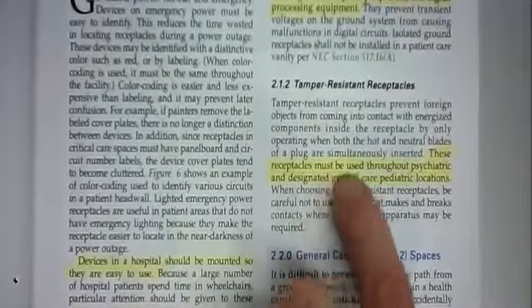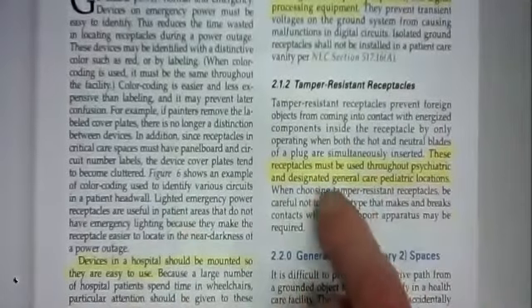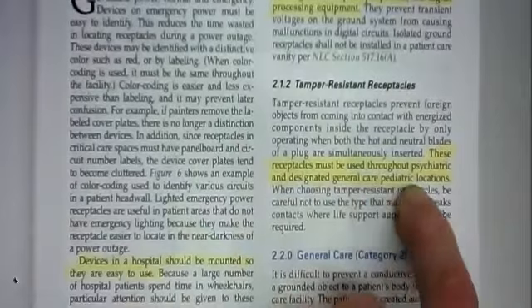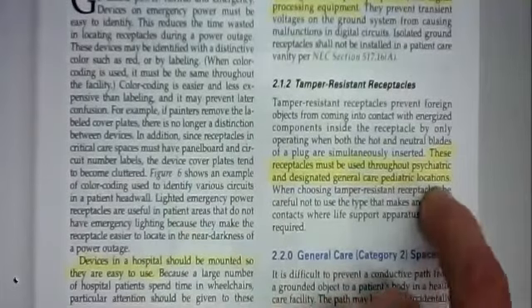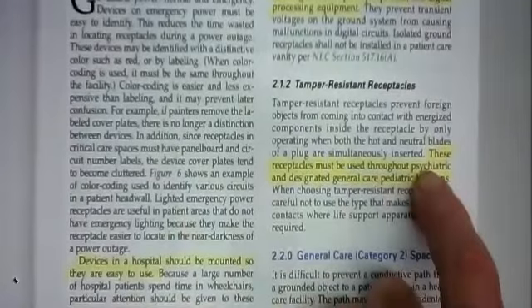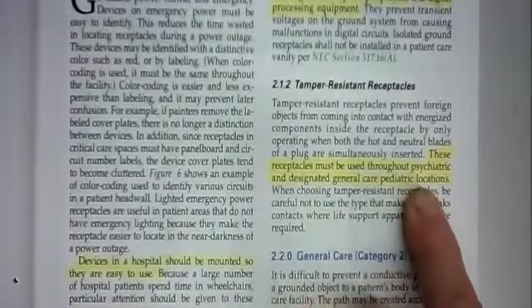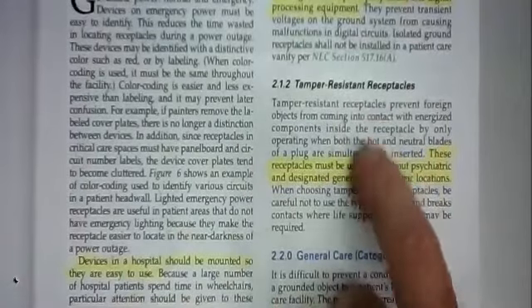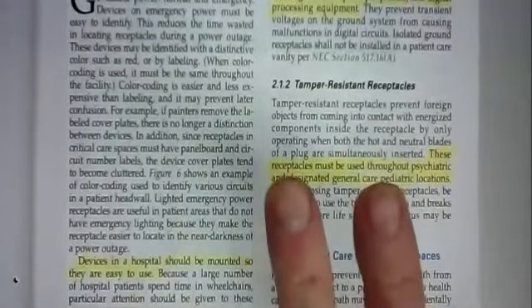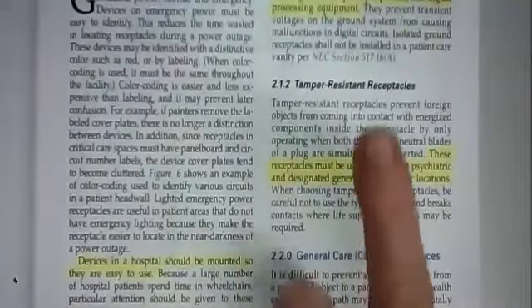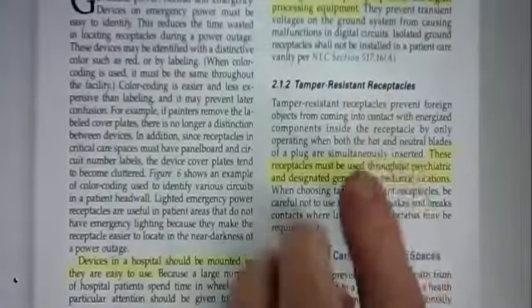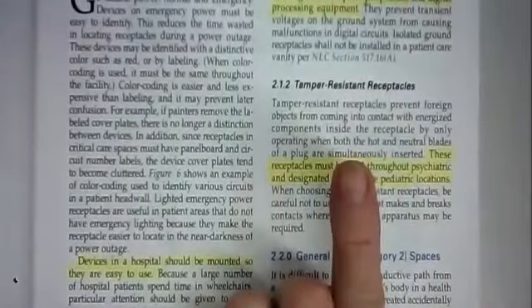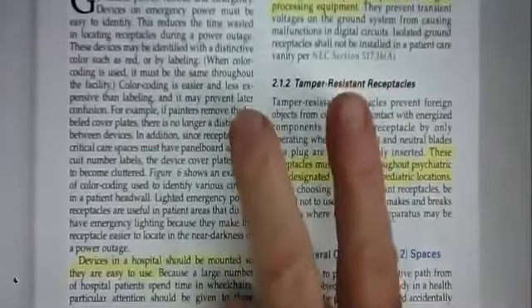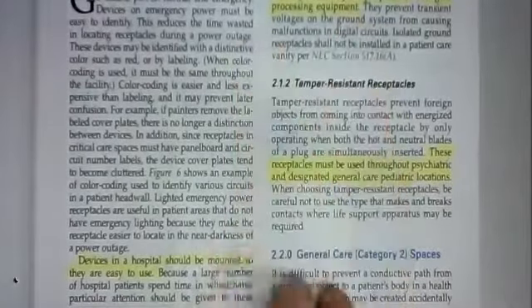Tamper-resistant receptacles. These receptacles must be used throughout psychiatric and designated general care pediatric, that's children, locations. So pediatric and psychiatric, people will stick things in those receptacles, so you have to have tamper-resistant. You have to put a blade in both sides, hot and neutral, at the same time in order to get them to plug in. You can't take a paper clip or a screwdriver or something and just push in on it. It's got a plastic window that keeps that blade from going in. When you push both of them, the window will move out of the way, and then you can plug into that tamper-resistant receptacle.